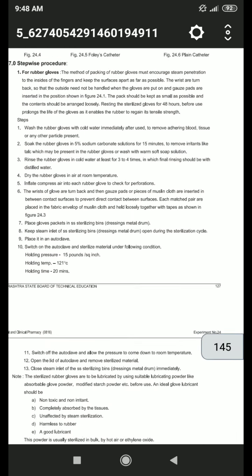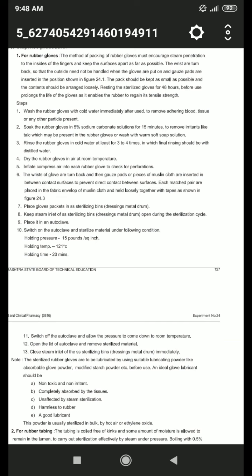Then next step, switch off the autoclave and allow the pressure to come down to room level. Then open the lid of the autoclave and remove the sterilized material. Then close the steam inlet of the SS sterilizing bins, that is the dressing metal drum, immediately. Then note, the sterilized rubber gloves are to be lubricated using suitable lubricating powder like absorbable glove powder, modified starch powder, etc., before use.